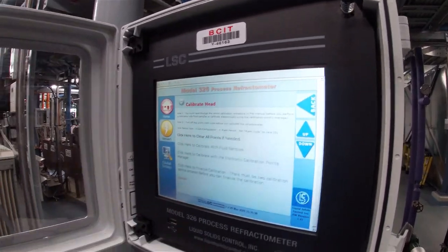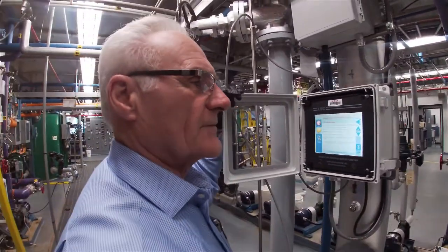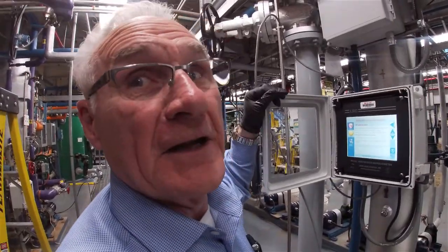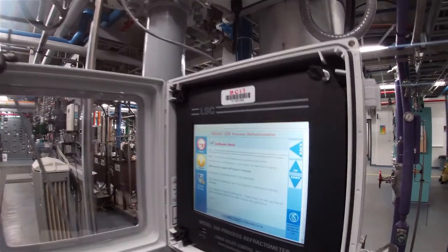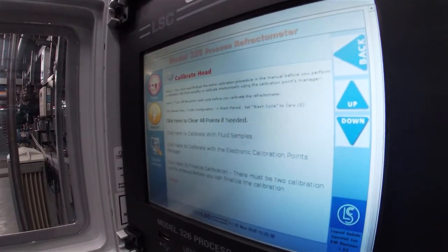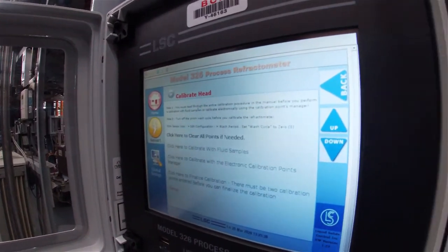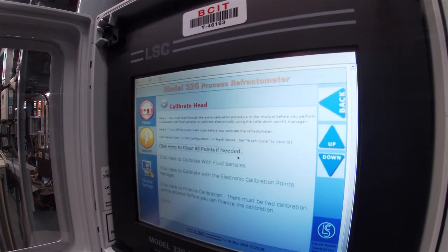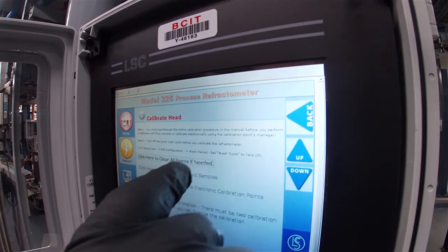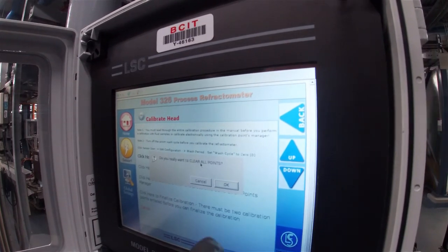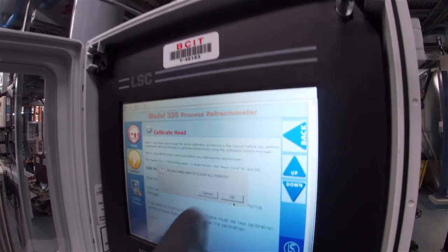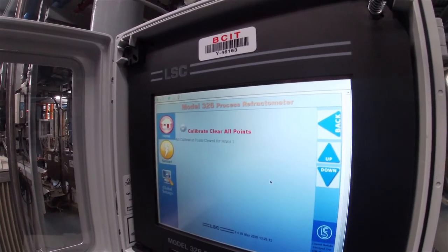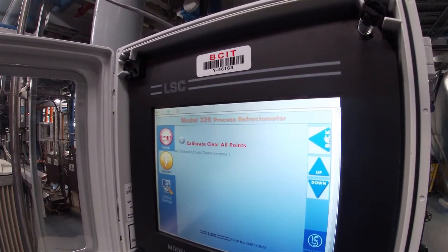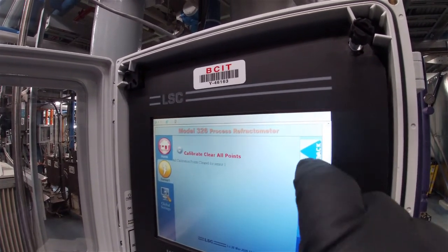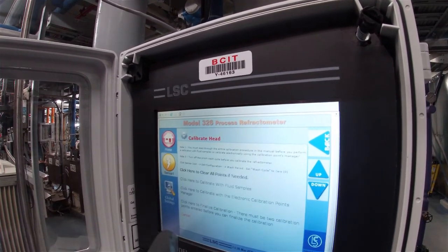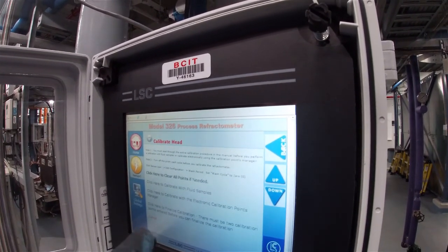What we should probably do is clear all of the points so that we don't end up with any left in there. We've run into problems. The factory set came with 5 points. We're only going to calibrate 3, and we ended up with some in-between bogus values. So you're better off clearing them. We're going to hit that one to clear, I think. And it says you really want to do it. It's kind of like formatting your hard drive. Yes. And so all the points are cleared. I'm going to go back and click here to calibrate with sample fluids, which is what we're going to do.